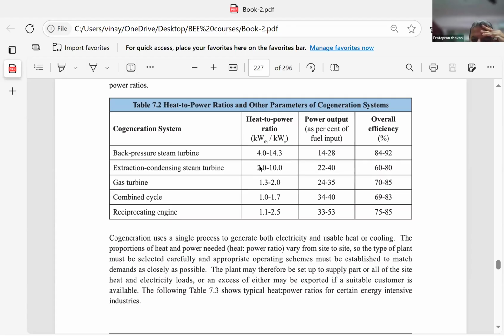Back pressure steam turbine has a high heat to power ratio. The extraction condenser type partially generates power and partially serves process needs, with a ratio of 2 heat to 1 electricity. Gas turbine improves this further, to 1.3 to 2. In combined cycle, when fully utilized, the ratio is 1, almost the entire heat is used for power generation.